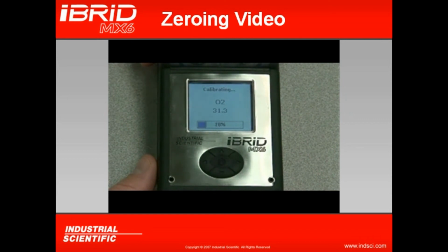Once again, if this oxygen concentration is any other number other than 20.9, it's then going to show a skewed calibration. But upon completing this, it'll show you that the zeroings have passed. Pressing on-off again acknowledges. On-off again takes you back to real time.